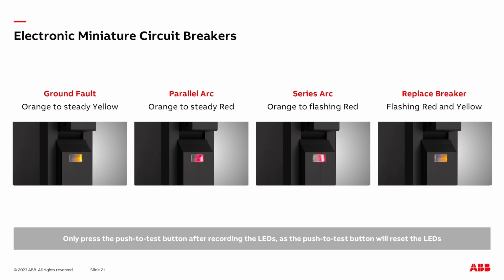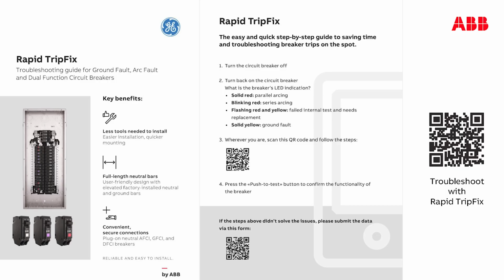After determining the LEDs, we recommend checking the wiring connections at the breaker, receptacles, and the attached equipment. Confirm if the breaker has any ground fault detecting capabilities and the breaker is not on a shared neutral. Also, confirm the load attached to the breaker when it is tripped is not pulling more amperage than the breaker is rated for. Some appliances with heating elements or motors can have an inrush current that can pull more amperage than the circuit wiring. When there is an issue, we want to help find the best solution for you.